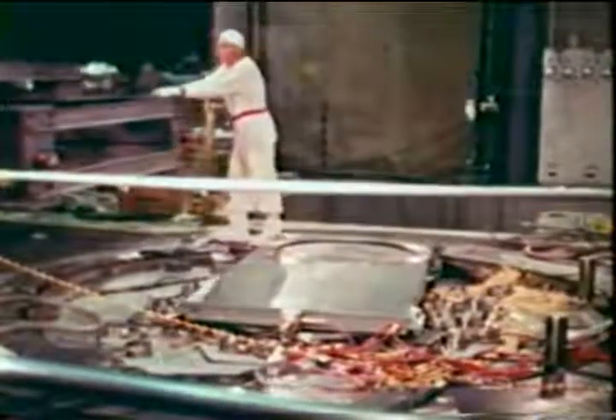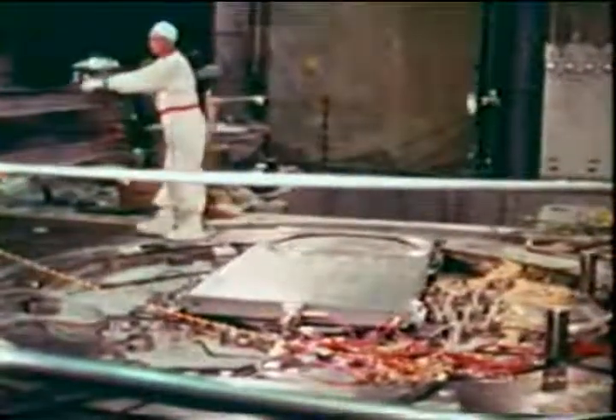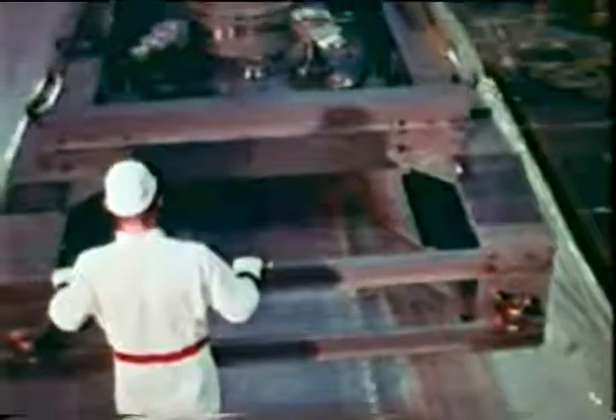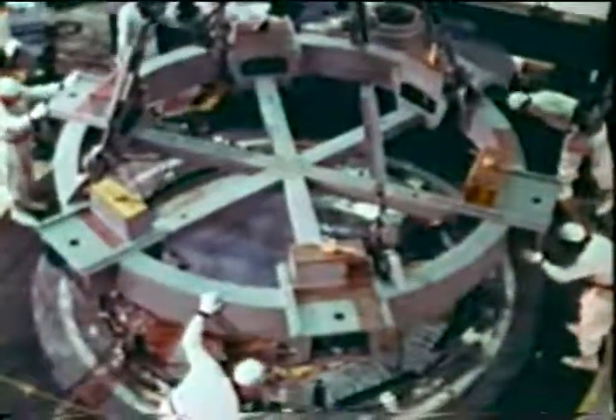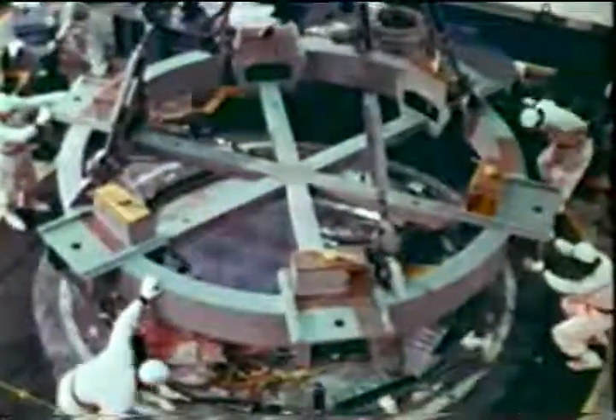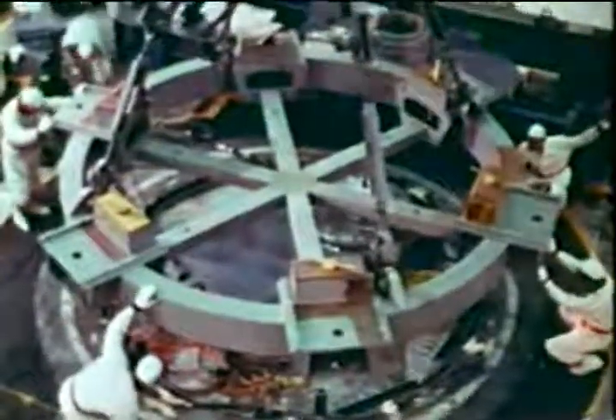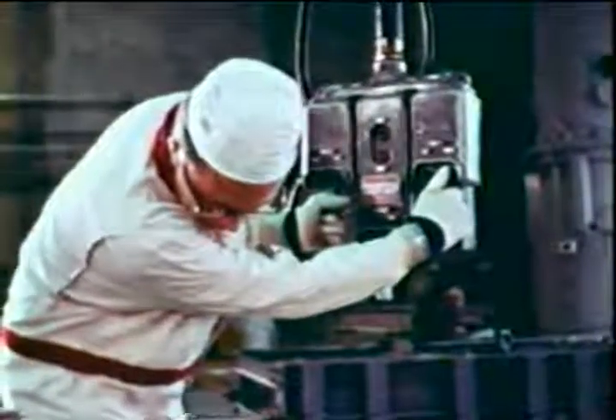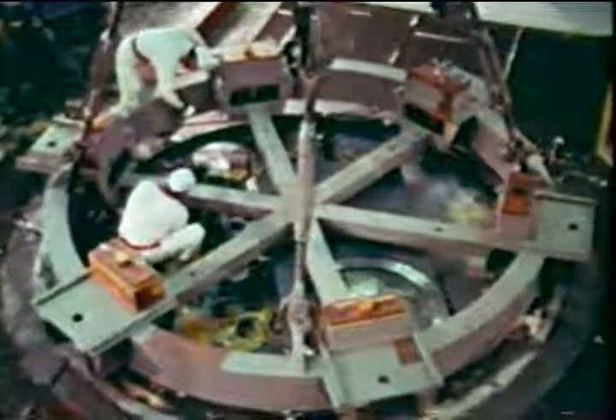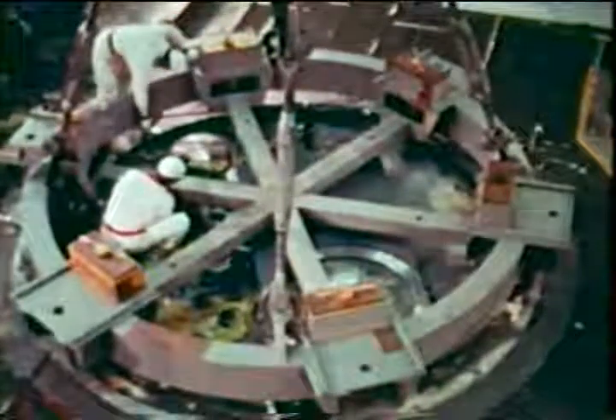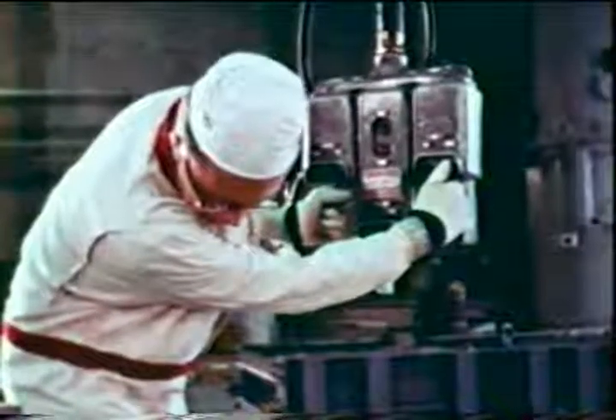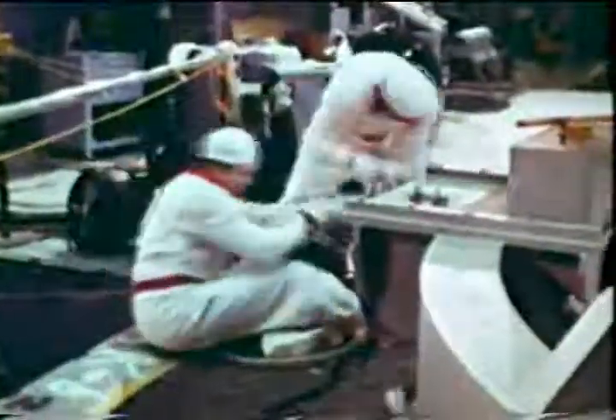After replacing all defective moderator cans which could be reached at one orientation of the top shield, the support bridge was removed. A massive lifting rig suspended from a swivel hook was attached to the 75-ton top shield. The Cerrobend metal seal around the top shield was melted. Then the top shield was raised slightly and rotated to a new position.